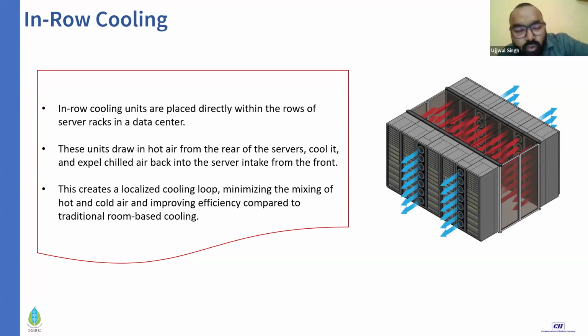You don't need a false ceiling, you don't need a false flooring, and you don't need a large pressure difference to pump air to your mechanical gallery and back through a pressurized plenum to your servers. So fan efficiency improves a lot, fan power consumption improves a lot, and since it's adjacent to the server area, the response time for any deviation in air temperature is much less compared to a normal cold aisle or hot aisle system.